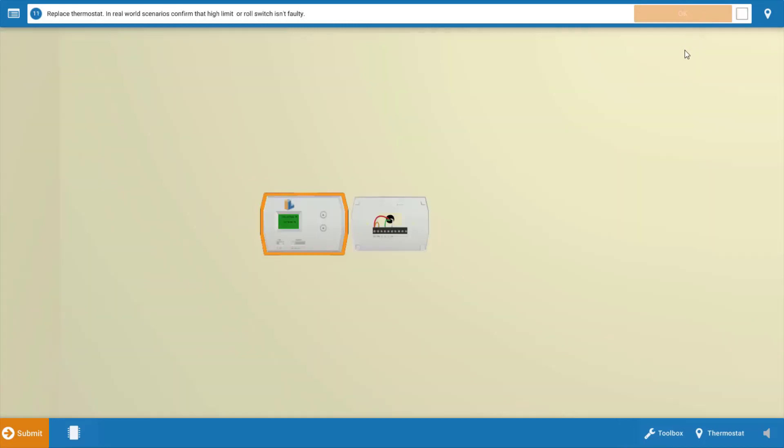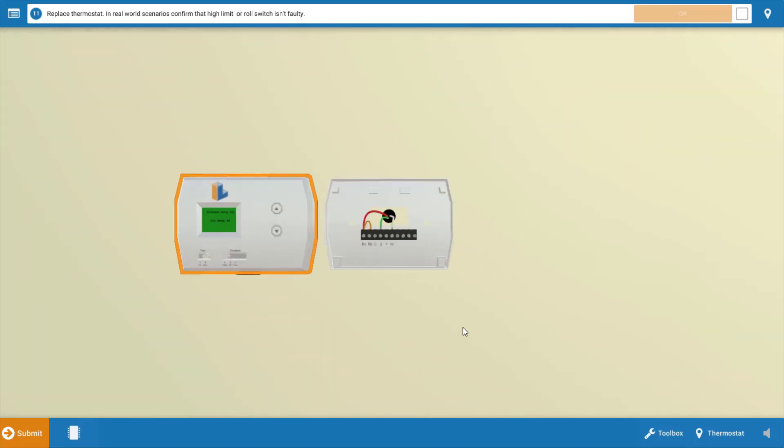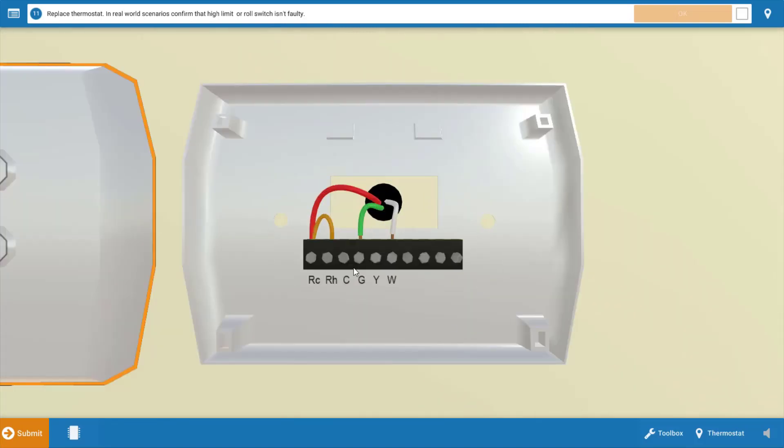But what you could do prior to replacing the thermostat is place a jumper across the RH and W terminals. Now if the unit comes on, that is further verification that the thermostat is bad. If after doing this the unit still does not start, unfortunately that means there's probably a break in the thermostat wires running from the thermostat down to the IFC.